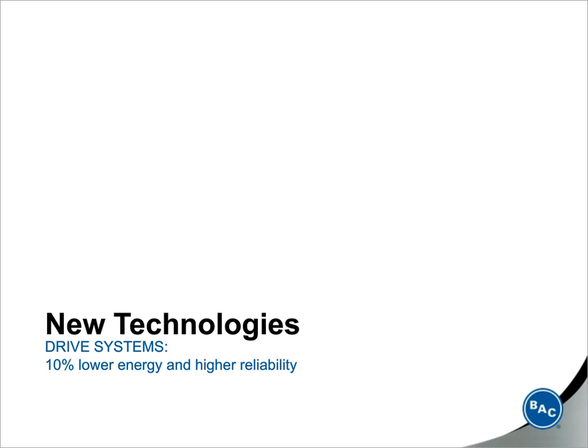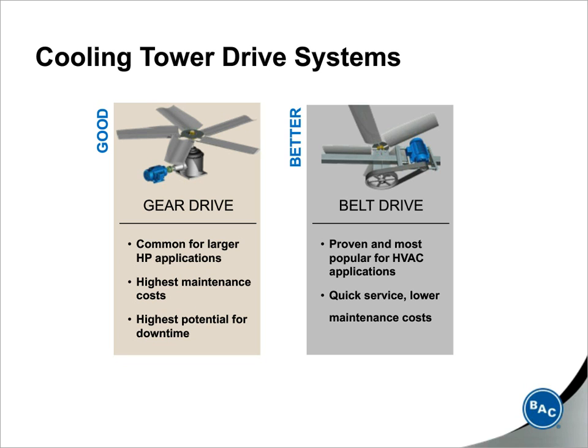So now, let's talk about how new drive system technologies can lower energy usage by 10% and can really greatly improve reliability. Traditionally, gear and belt drive systems have been used in factory-assembled cooling towers for years, and belt has really gained popularity and acceptance and has become easily the most common drive system in the market. Belt drive systems have definitely become more reliable over time, due in part to better system and drive designs, and also because VFDs are used much more frequently than they used to be. VFDs provide soft starts on the mechanical components. Belt systems are also much less expensive and much easier to replace than gears when gear systems go down.